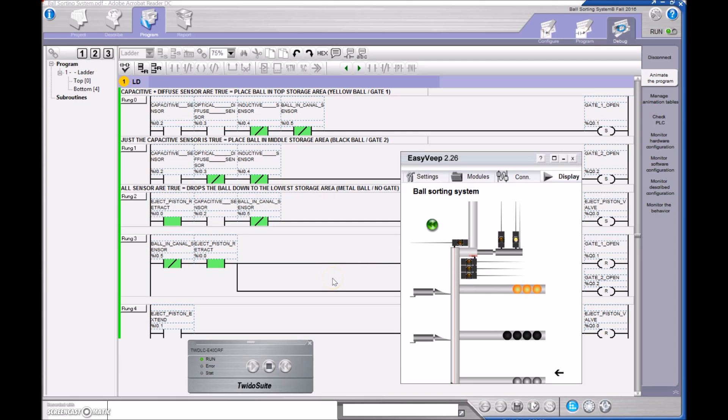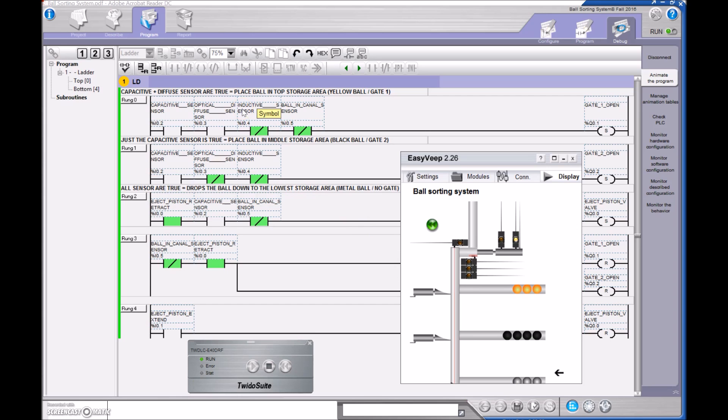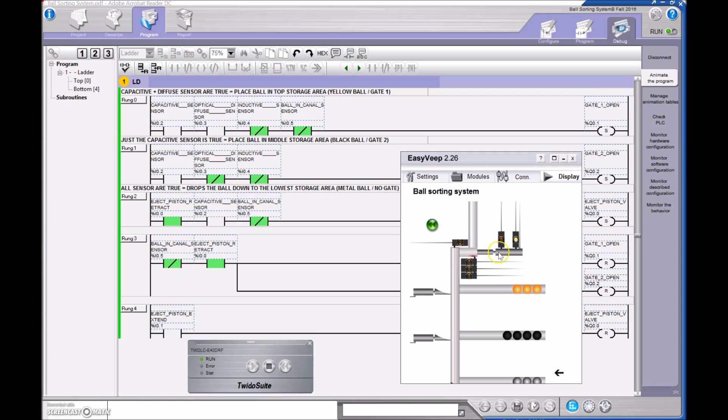In addition to that, if all the sensors are true, that would be this guy right here, because the capacitive sensor would be true, the diffuse sensor would be true, and the inductive sensor would be true. Rather than putting all those guys in there, I left all of them out. And I'm just saying that if the capacitive sensor is true and there's nothing in the canal, then start to energize this eject piston right here and push that ball out. And that ball, if none of these single-acting cylinders are activated, then that ball is just going to travel all the way down to the bottom.